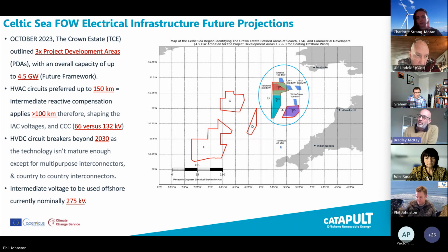So I think that's going to affect it substantially. But I think with 132, because of the current carrying capacity, we're going to be able to up that to suit the 15 megawatt turbine. I think that's really going to show compared to a 33 or 66. So like Charlotte was saying in the presentation, it's so important that we get that standardization in the correct line, and we start that work now, otherwise I think those risks and reliabilities are going to be an issue.